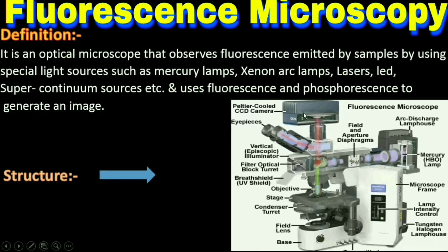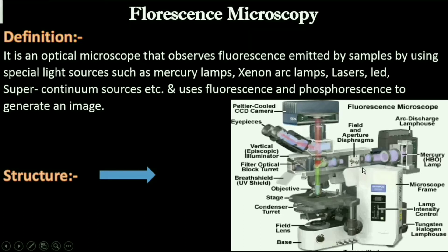The main components of this microscopic technique are: first, the light source; second, the excitation filter — also called the first optical filter; third, the dichroic mirror or beam splitter; fourth, the objective lens; fifth, the emission filter; and last, the detector, which detects the image using CCD cameras. Other parts are the same as the compound microscope; the main difference is in the light source.